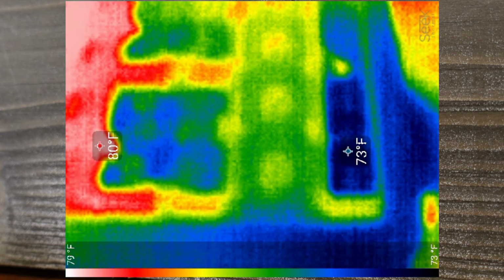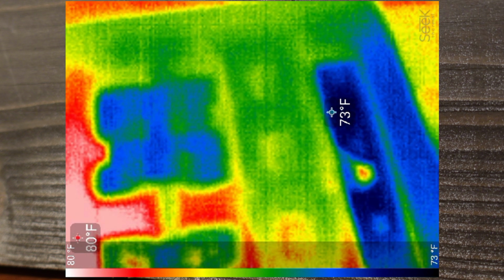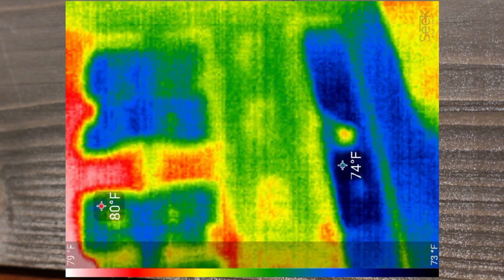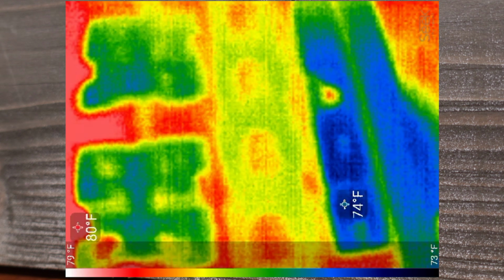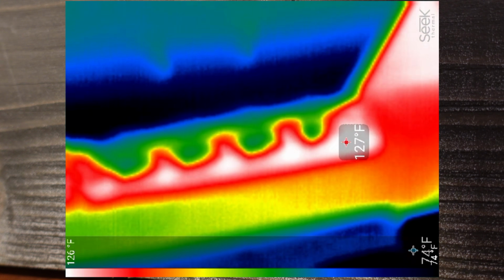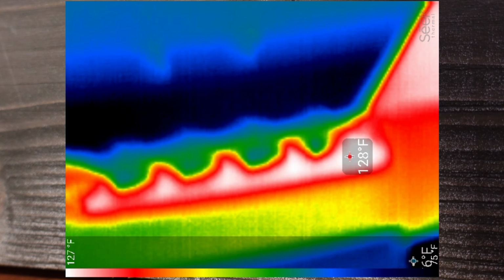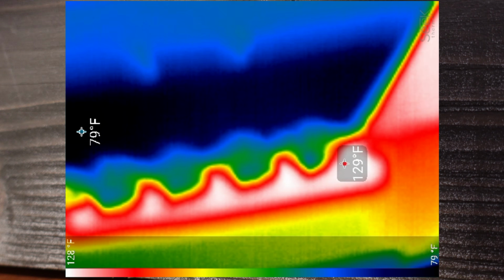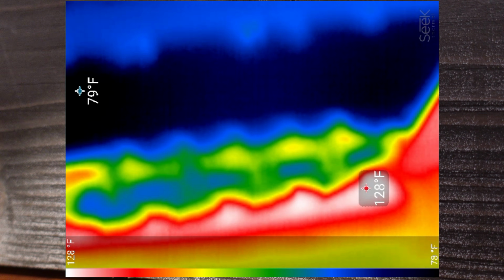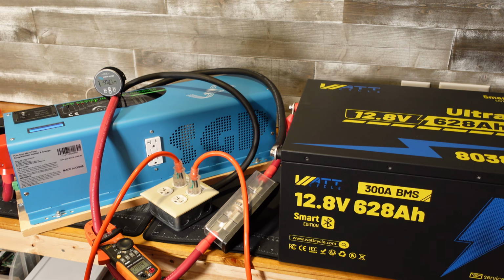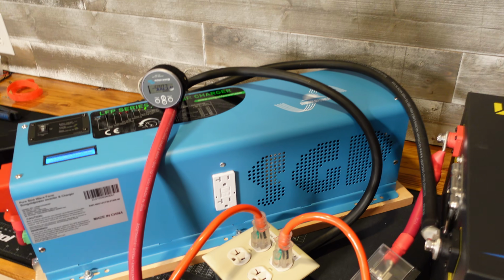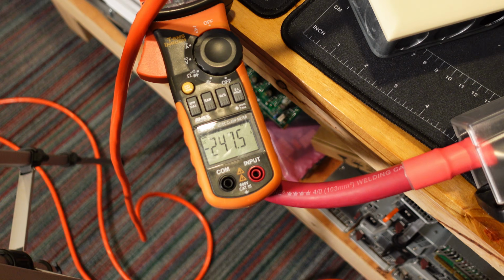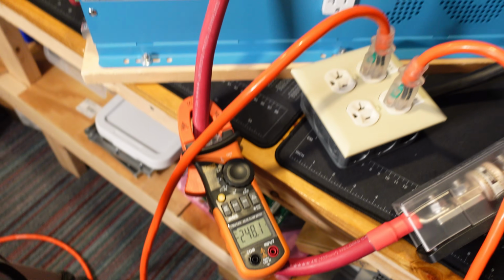Taking a look at the thermal camera, I don't really see any noticeable hotspots on this battery. It actually looks pretty good, which was consistent with our original testing. If we try to take a look down at the BMS, it looks like the terminals on the BMS are sitting at 128 degrees Fahrenheit there, 126. We're at 2 hours and 15 minutes and the test is still running. We are pulling 248 amps there.